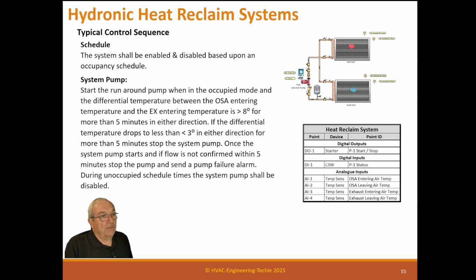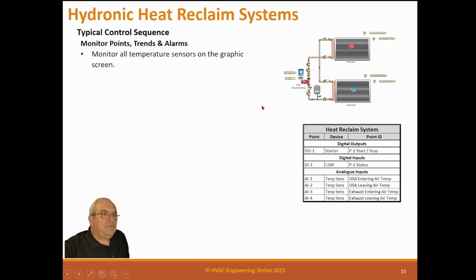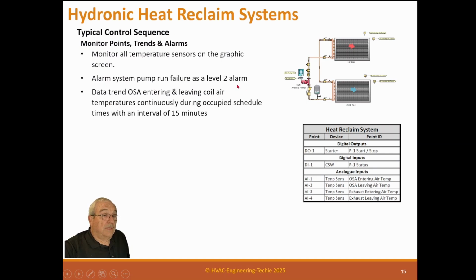Stop the system pump after the differential is less than 3 degrees for more than 5 minutes. Once the system pump starts, if flow is not confirmed within 5 minutes, stop the pump and send a pump failure alarm. During occupied scheduled times, the system pump is enabled; in the unoccupied time, the pump should be disabled. There's no reason to do this during unoccupied times. So monitor all temperature sensors on the graphic screen. Alarm system pump run failure, level 2 alarm. Could be a level 2 alarm.